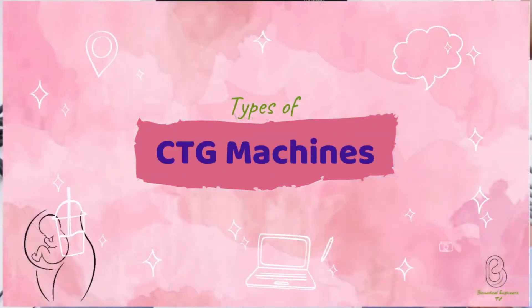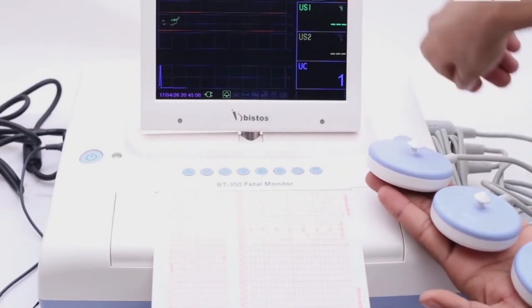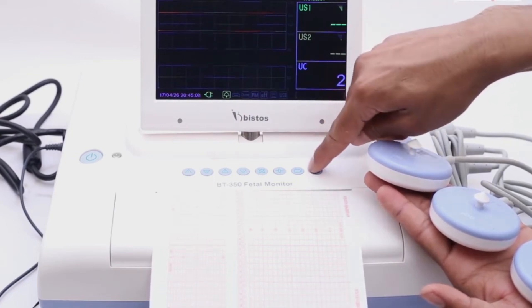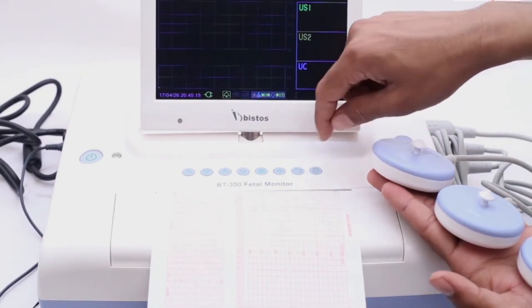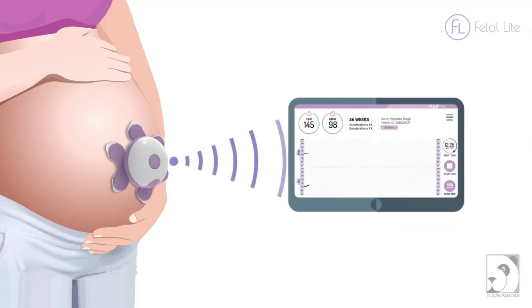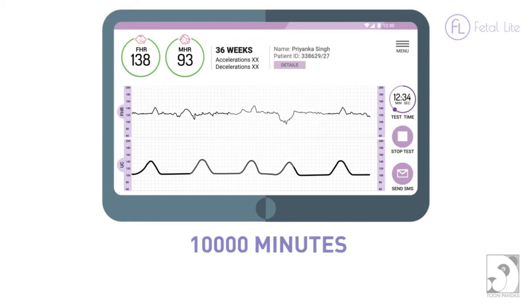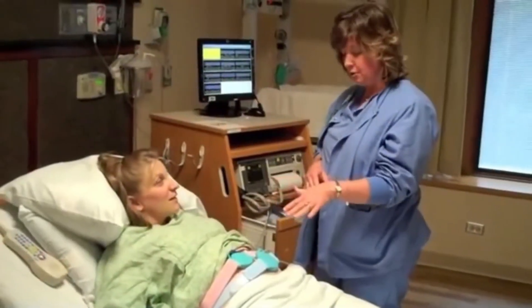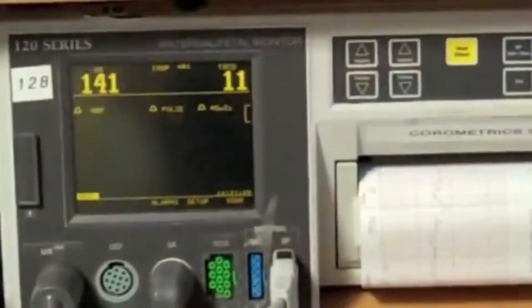CTG machines can be classified as conventional fetal monitors, wireless fetal monitors, and central station-based fetal monitors. Conventional CTG machines are stand-alone machines with a wired ultrasound transducer, tocotransducer, and event marker. In wireless CTG machines, the ultrasound probe, tocotransducer, and event marker are connected wirelessly to the main device, continuously monitoring the patient without any cables. Central station-based fetal monitoring is used in obstetric and gynaecology departments where more than one patient can be monitored at one place, with multiple CTG machines connected to a central station by wire or by medically graded wireless communication.